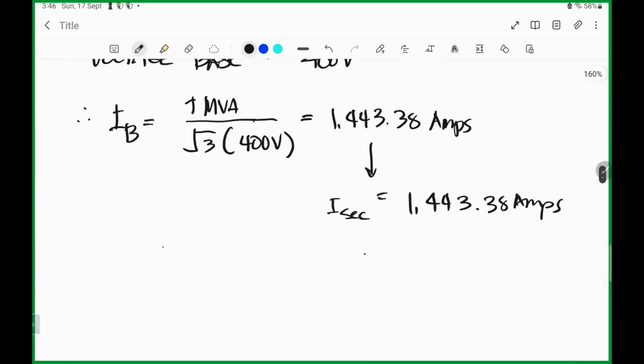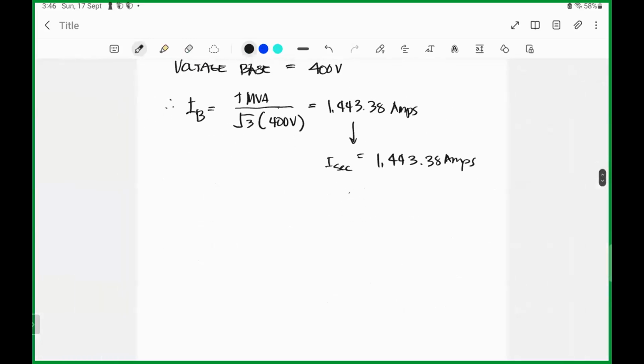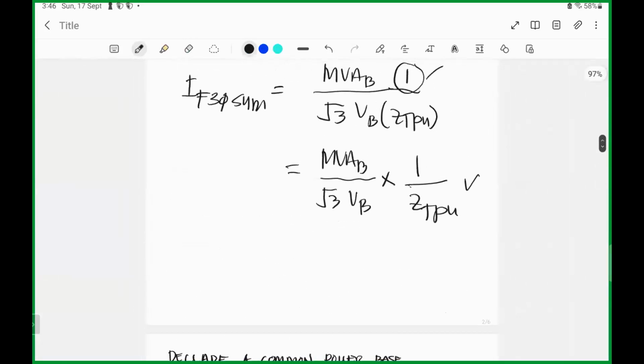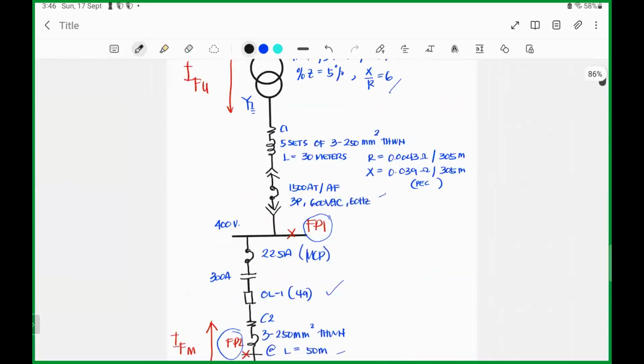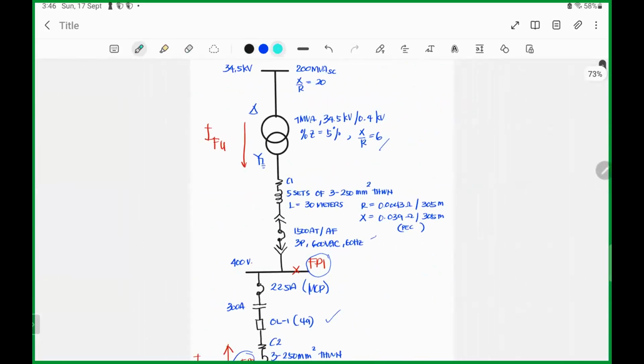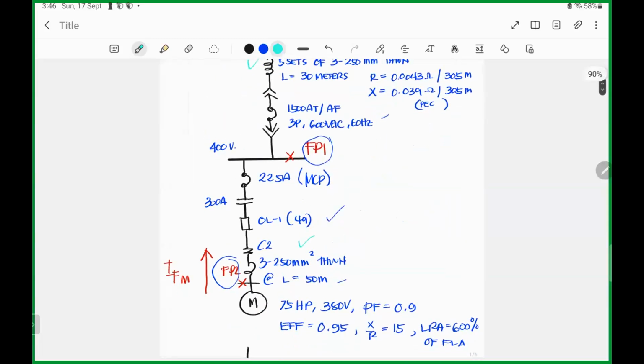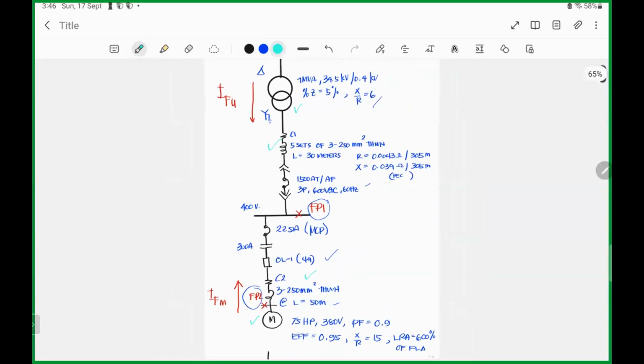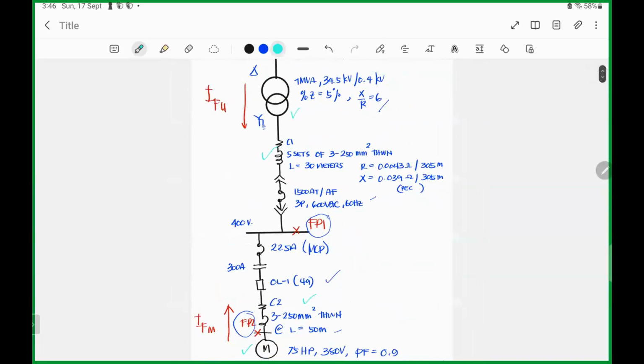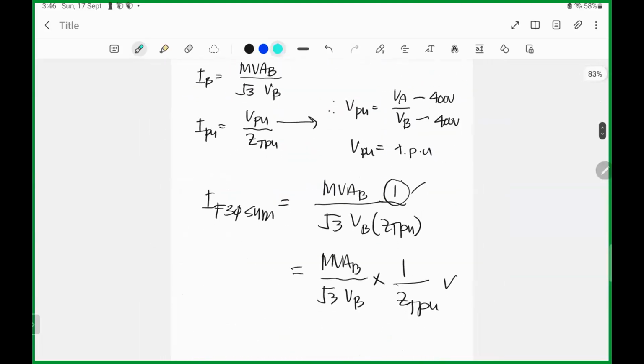So now, let's convert the per unit values of these electrical components located in the system. So we have to convert the utility, which is a source of fault. We need to convert the transformer in per unit values, the cable, and the cable 2 plus the motor. Okay? So as you can see here, I provide a flow of current fault. Pag hinanap natin yung fault sa fault point 1, the contribution will be the utility plus the motor. Okay? So let's calculate now the conversion.